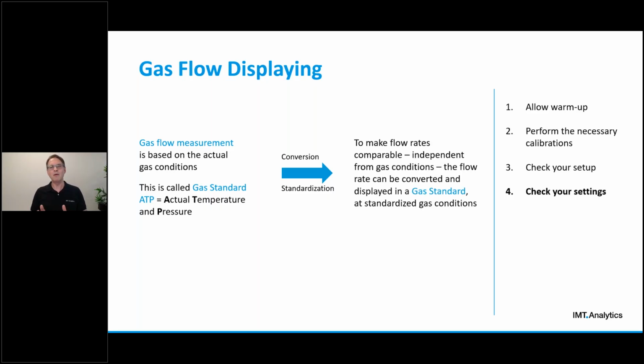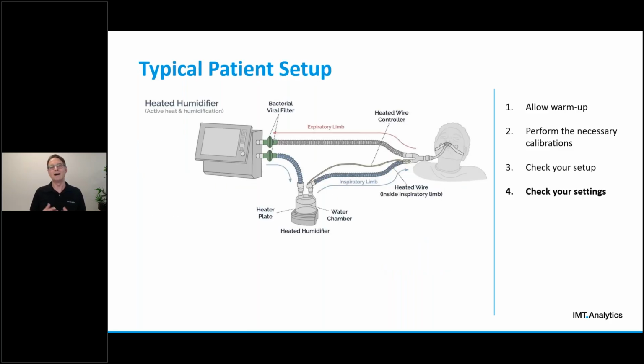For example, how much flow would that be if the gas was, let's say, 40 degrees Celsius in temperature and 90% humid, even if it wasn't at the time we measured it. And we call this process gas flow displaying. So we have a separation between what we measure and what we display. So now you might ask, why do we need to care about that? Let me talk about the practical part of it.